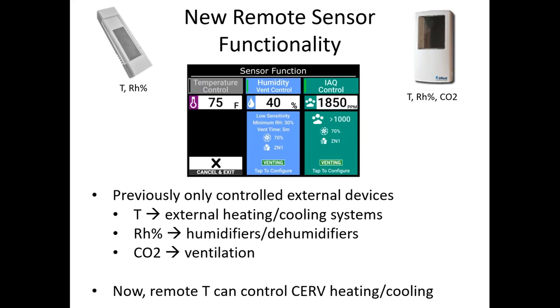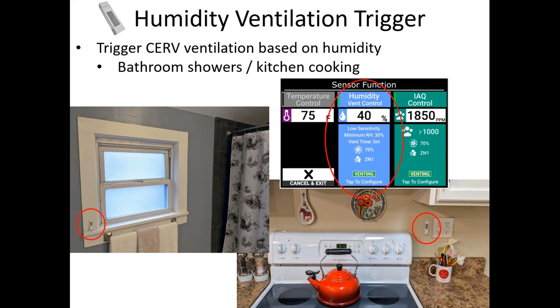Humidity ventilation trigger. This uses that same temperature humidity sensor to activate ventilation in the CERV based on humidity. You can see in these pictures, on the left-hand side, the sensor is located in the bathroom. So this would be for triggering ventilation from a shower. And then the bottom right shows the sensor located near the cooktop. So cooking, producing humidity that way, can also trigger ventilation.